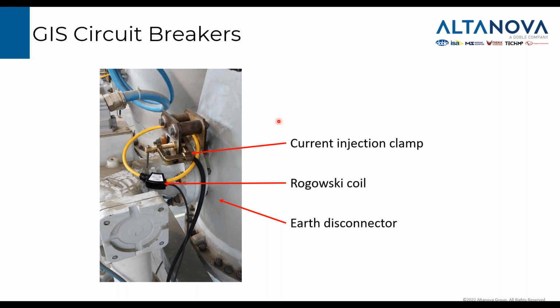This is an example. This is the earth disconnector. So you can see that we are not going to unscrew anything. The earth disconnector can remain closed. This is a special clamp, because not always you can put standard regular clamps. Maybe you need something like this. And here you place the Rogowski coil. In this way, you can detect the current variations due only to the flow into the main contact.